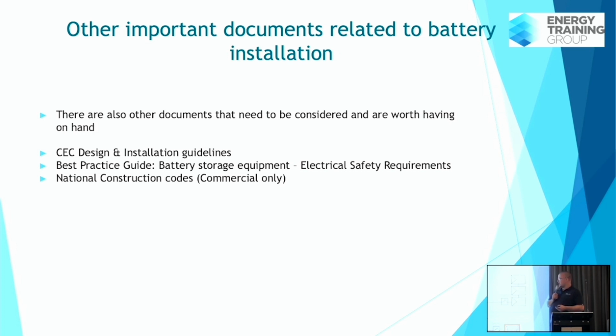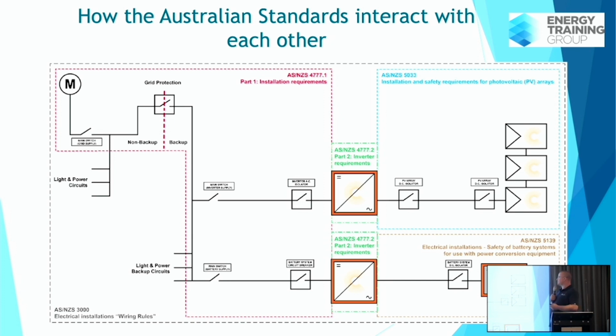This is showing you where each standard applies. AS3000 applies to the entire installation - you always need to comply with that as an electrician. 4777.1, as you can see, is the AC side of the installation. The inverters must comply with 4777.2. Your PV array must comply with 5033, and your battery installation needs to comply with 5139.